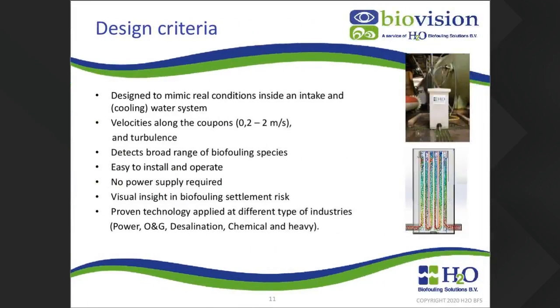Now, the design of our monitor, which is called the BioVision monitor, what we try to do is to mimic the conditions inside an intake and cooling water system. So we have a monitor where 5 fouling coupons are installed, and along the coupons there is a range of water velocities of 0.2 to 2 meters per second, which mimics more or less the general range of velocities in an intake and cooling water system. In addition, there is turbulence in the monitor, which is favorable for specific species like mussels.